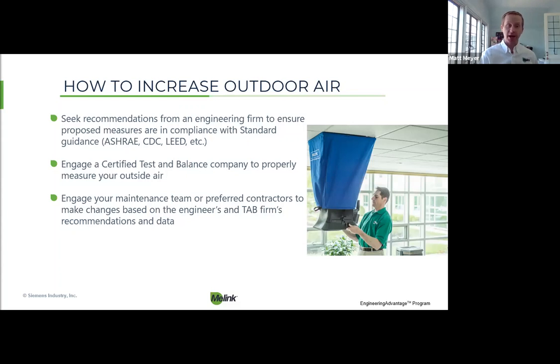The next step is to have a certified TAB firm, test and balance, come in and properly measure all your air, not just your outside air. Then those two sources will be able to provide you with the proper recommendations to tell your maintenance team or your preferred contractor to come out and actually make changes to your building. Next slide, please.